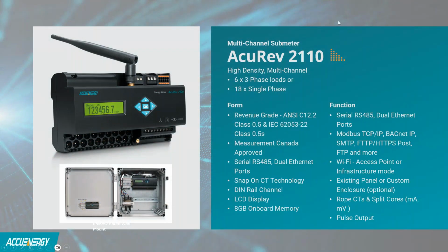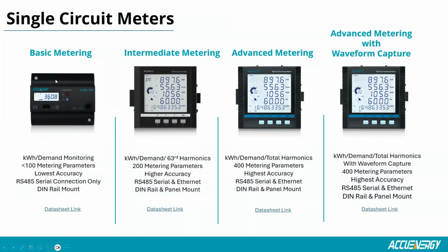We also have multi-circuit meters, the AccuRev 2100 or 2110, capable of monitoring up to 6 three-phase loads or 18 single circuit inputs. Here are the high level specs—I won't go into all of them, but from a data point and communication interfacing standpoint, we have every solution you need, whether connecting via BACnet, IP, or MSTP. All communication protocols are available with this multi-circuit meter, and that also applies to the single circuit meters, with the exception of the basic AccuRev 1300, which is RS-485 connection only.